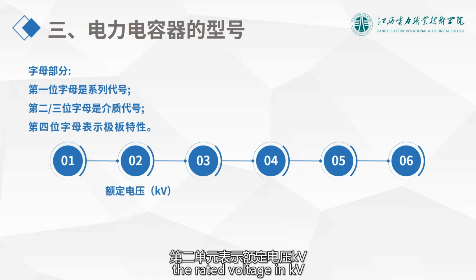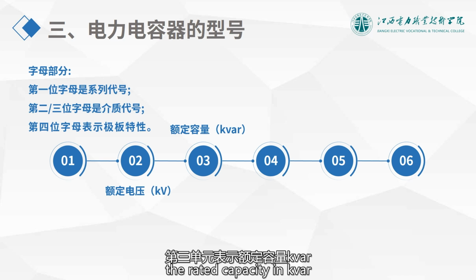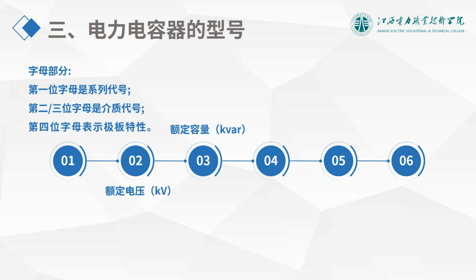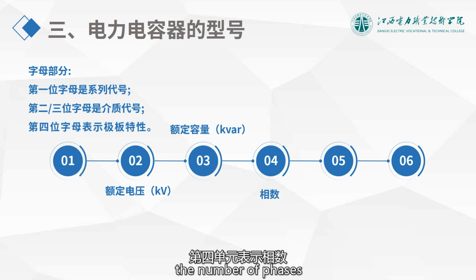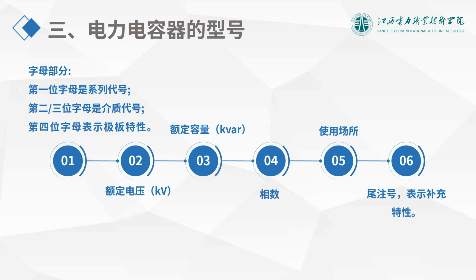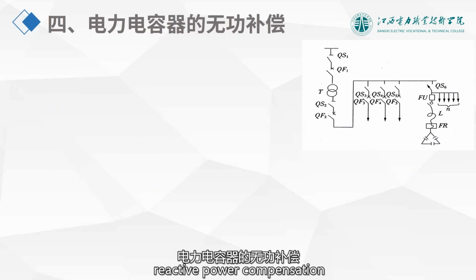The second unit indicates the rated voltage in kilovolt. The third unit indicates the rated capacity in kilovar. The fourth unit indicates the number of phases: 1 for single phase, 3 for three-phase. The fifth unit indicates the usage location: W for outdoor use, no marking for indoor use. The sixth unit indicates the suffix code, indicating additional characteristics. Next, we will introduce reactive power compensation for power capacitors.